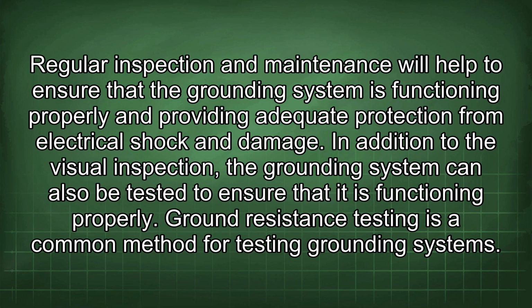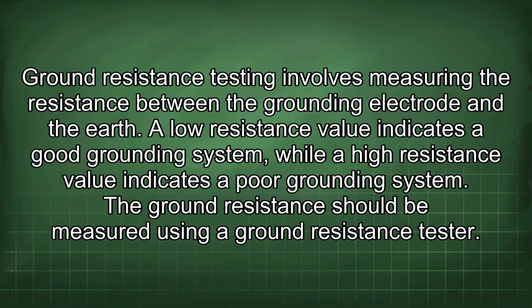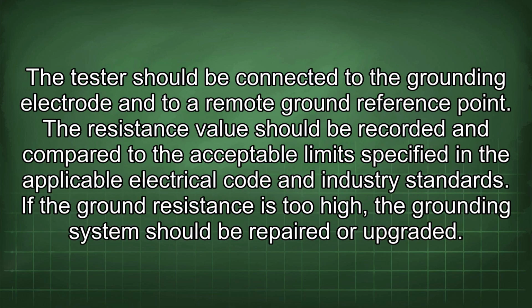In addition to the visual inspection, the grounding system can also be tested to ensure that it is functioning properly. Ground resistance testing is a common method for testing grounding systems. Ground resistance testing involves measuring the resistance between the grounding electrode and the earth. A low resistance value indicates a good grounding system, while a high resistance value indicates a poor grounding system. The ground resistance should be measured using a ground resistance tester. The tester should be connected to the grounding electrode and to a remote ground reference point.